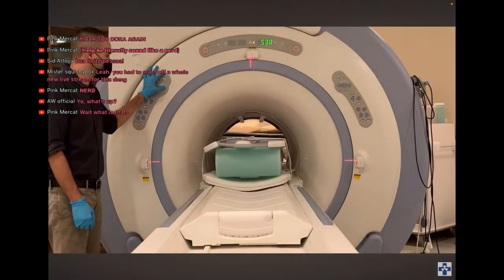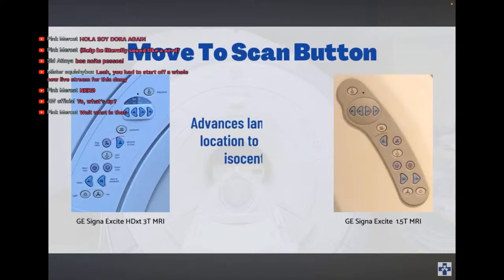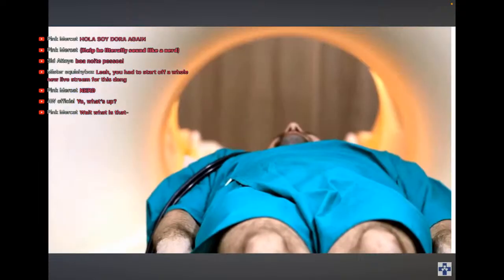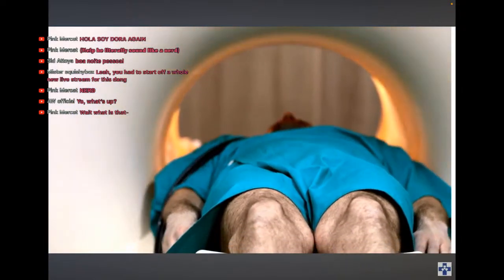The slow in and slow out buttons move the patient table at a rate of half an inch per second for precision landmarking. The landmark button bookmarks the location defined by the laser alignment lights. Once the landmark has been set, the Move to Scan button automatically drives the patient table towards the magnet ISO center. Stop Move immediately halts all in and out cradle functions.